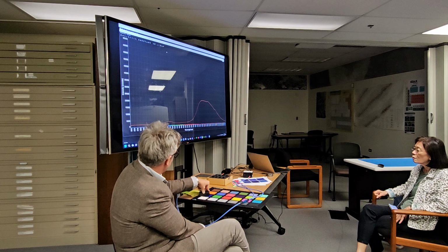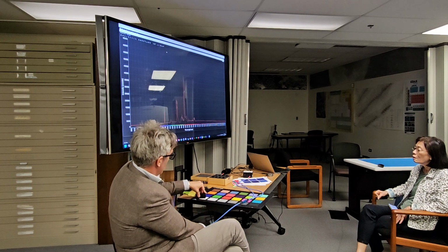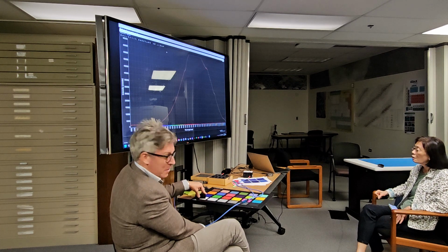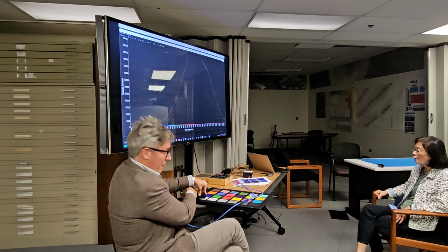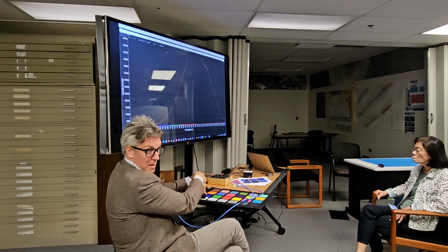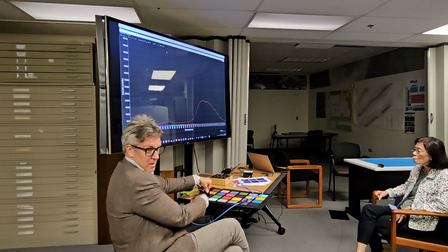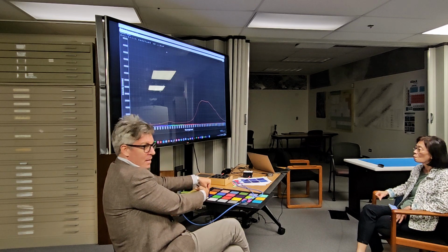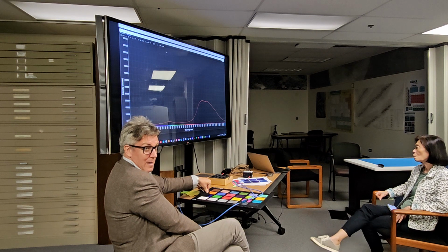Now, I turned the integration time down on this so that we didn't saturate. We're saturating on a highly reflective target, but this blue is much darker. So even for the same input of photons, I haven't changed anything associated with the lamp, the amount of light that the spectrometer measures is lower because this is a dark blue. And we also have that blue peak imprinted on it.